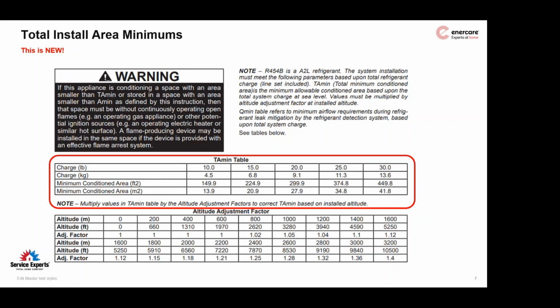Anyway, basically what I'm trying to say is there's now a total area minimum based on your system's total charge. That includes piping and any additional refrigerant charge for piping. If you've got a larger indoor coil for, say, a heat pump you're pairing up because you want better heating output, or it's a matched system for AHRI compatibility, or you or your homeowner is going to get a rebate, you may need an additional charge that might push it over the 10 or 15 pounds.